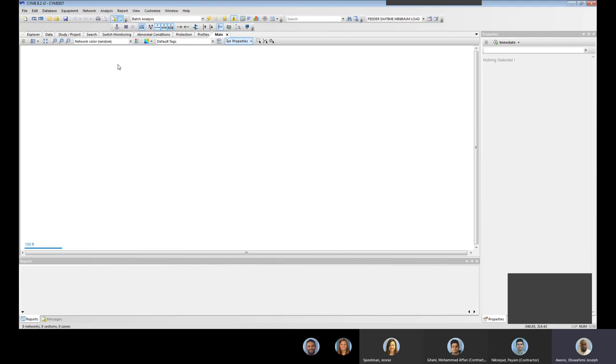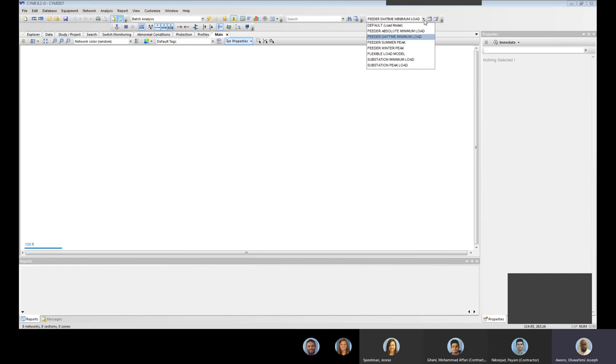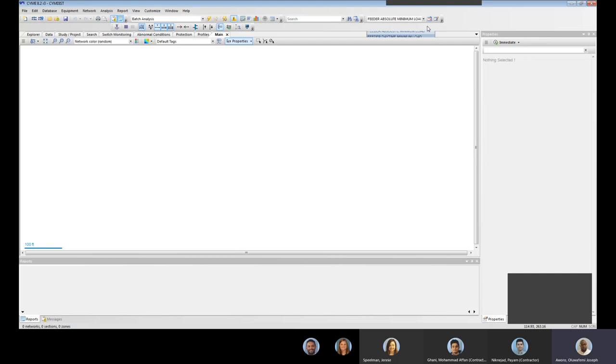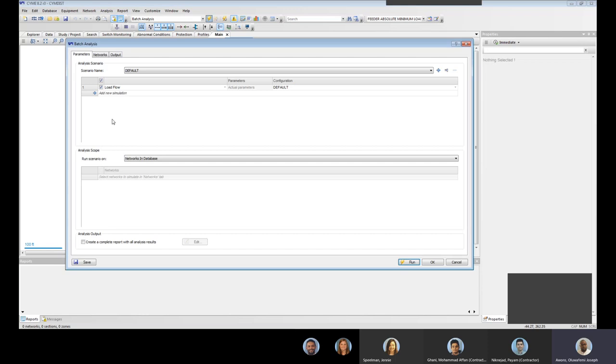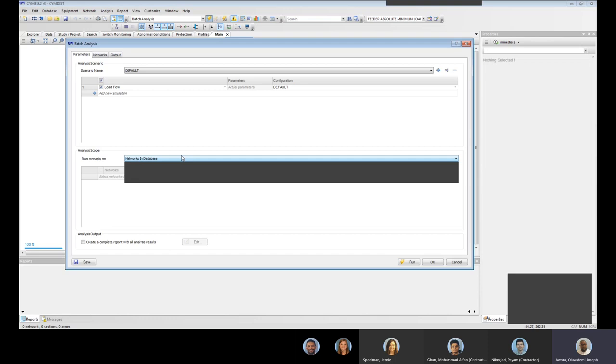So let's go through CYME right now and see how we can quickly run batch analysis. I will normally run the batch analysis for minimum load, basically the absolute minimum load or the peak season. When we run it for the minimum load we are interested in the high voltage feeders. So in the parameters tab everything looks, you leave it in the default. You have a load flow, the analysis scope is run scenario on networks in database except you want to look at self-contained files.